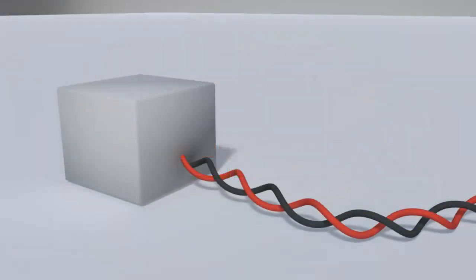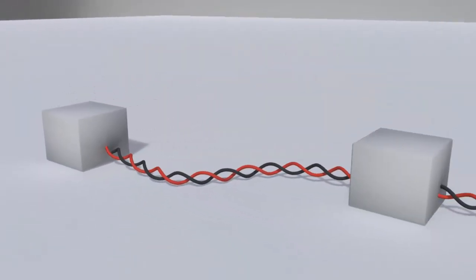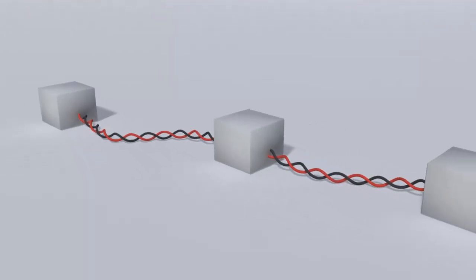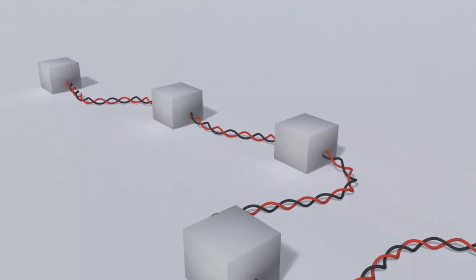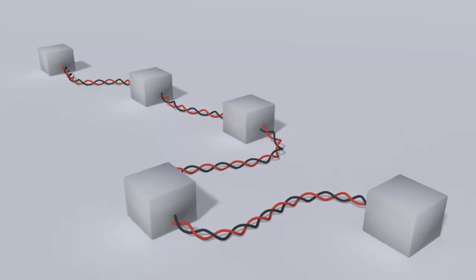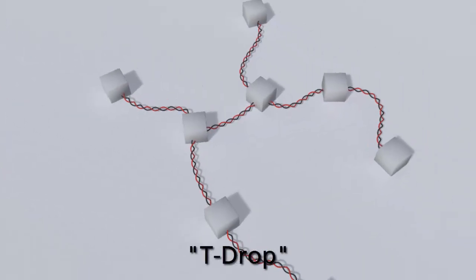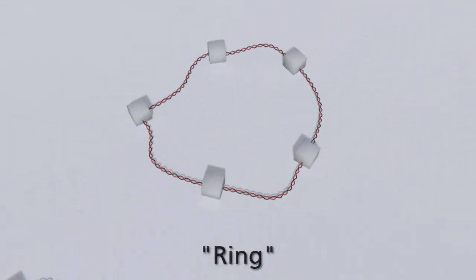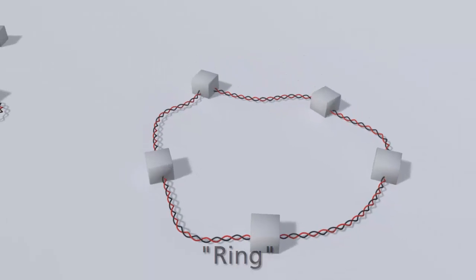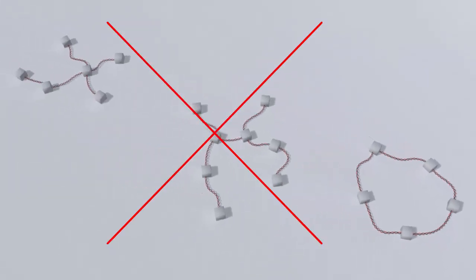The ideal layout of an RS-485 network is a daisy-chain architecture, with the master device located at one extreme end. This tends to minimize the possibility of signal collision. Star, t-drop, or ring-type topologies are strongly discouraged, as they can cause serious communication problems.